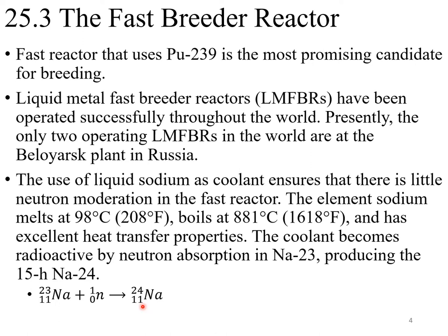Great care must be taken to prevent contact between sodium and water or air, which would result in a serious fire accompanied by the spread of radioactivity. To avoid such an event, an intermediate heat exchanger is used in which heat is transferred from radioactive primary sodium to non-radioactive secondary sodium.